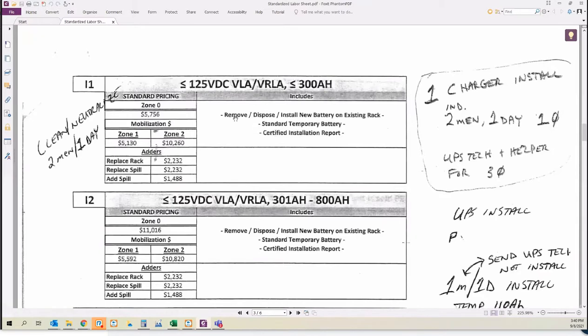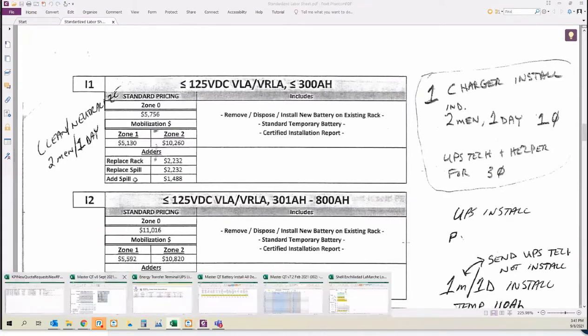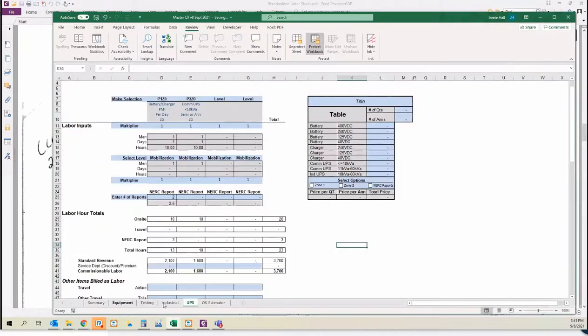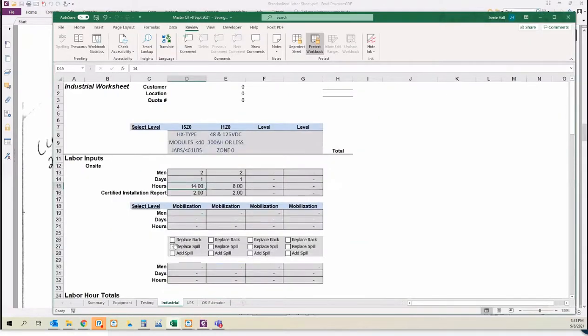For installation, we can R&R, they call it dispose, but it's remove and replace, and we dispose of the old one. So we remove it, replace it, dispose the old one, and install a new battery on the existing rack. Remember, we have the rack adders, so if we're doing it on the existing rack, under the industrial tab, you don't have to do replace rack.